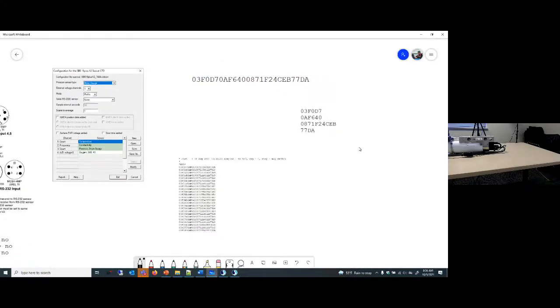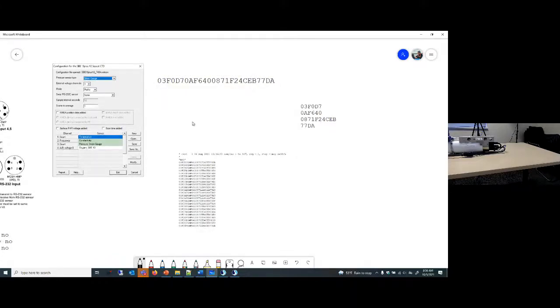So in this case, we can look at this data string and actually break it out into specific strings of data. So the first 6 characters are your temperature data. The next 6 characters are your conductivity data. And the next 10 characters are your pressure and your pressure temperature. So it's temperature, conductivity. And then any additional voltage channels you have enabled will add 4 extra characters at the end of your string here.